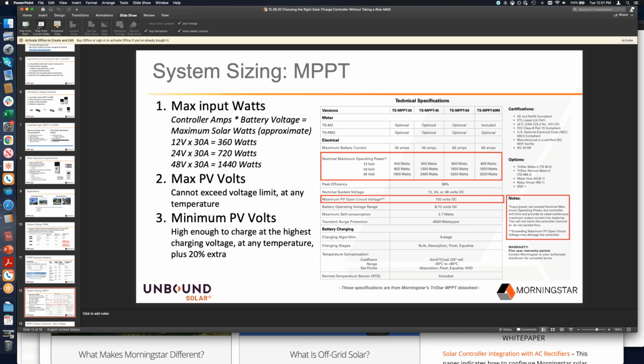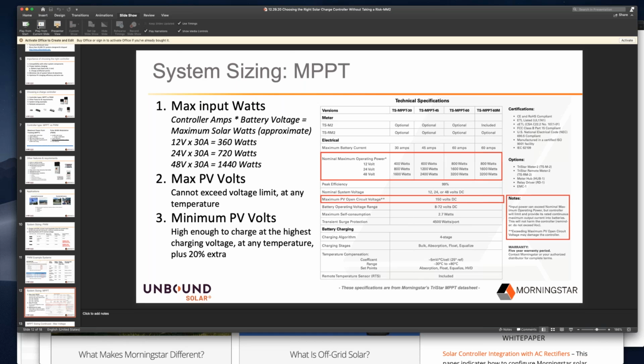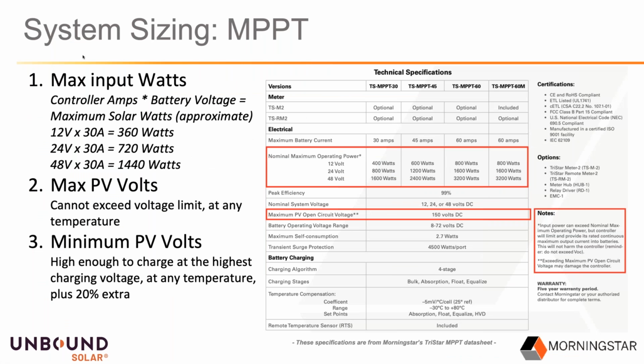You just take your wattage times efficiency, 99%, divided by the charging voltage. Your absorbed voltage is what you'd use here, not your float voltage. So 6.8 amps. Another way you could look at this is 6.8 amps times 14.5 volts is about 99 watts. There's some rounding error there. Hopefully that helps. That's how I would do the math. Okay, yeah, I think that clears that up. Thanks for that question, Joy.